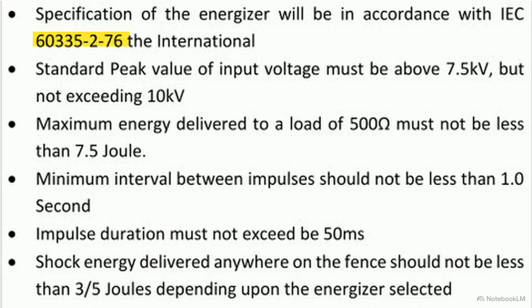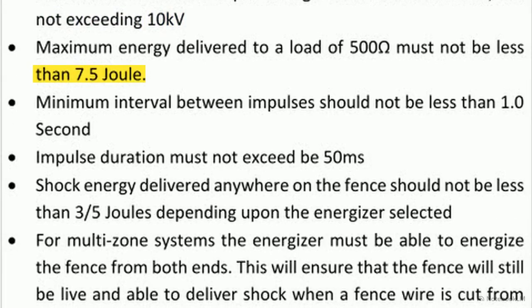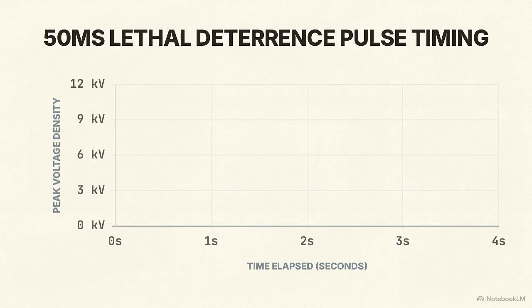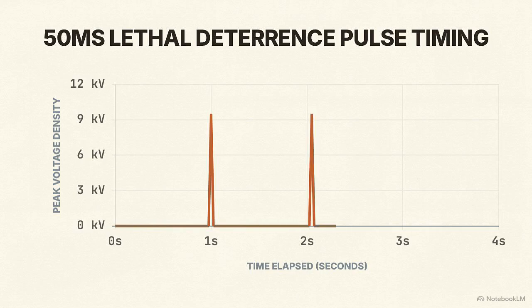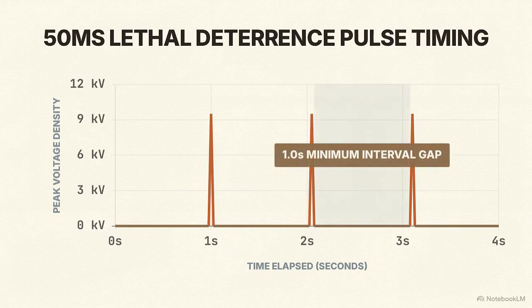The electrical architecture is governed by International Standard IEC 60335-2-76. The peak input voltage must sit between 7.5 and 10 kilovolts. The energizer must deliver 7.5 joules into a 500 ohm load, ensuring 3 to 5 joules of shock energy. This waveform graph visualizes the exact timing of the delivery. The system fires a sharp electrical spike lasting no more than 50 milliseconds, followed by a flat minimum 1-second interval gap before the next strike.